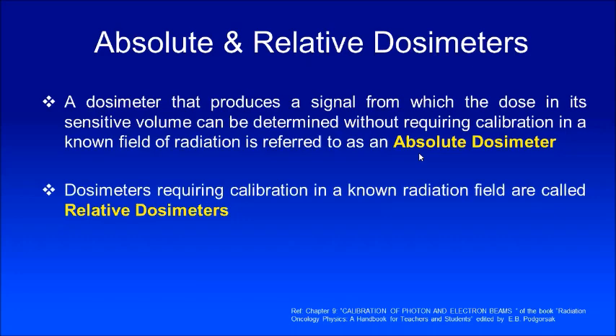Then what do we do in our lab? When we measure the linear accelerator dose, can we call it absolute dose? It is not measurement of absolute dose — you measure absorbed dose. Your dosimeters are called relative dosimeters because they require a calibration. You always calibrate it in a secondary standard dosimeter laboratory. So what you measure in your LINAC is absorbed dose measurement — it is not absolute dosimetry. I have also been thinking differently, because most companies sell the ionization chamber as an absolute dosimeter.